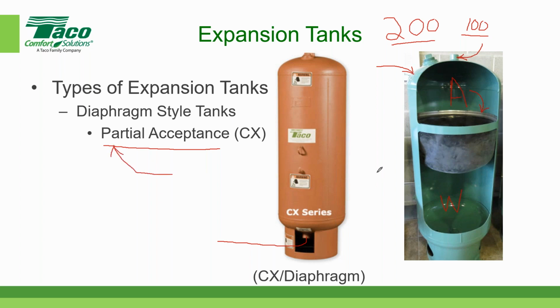Now, one of the major benefits to a diaphragm style tank is that they're very inexpensive. But the downside is that the bladder or diaphragm cannot be replaced. It cannot be serviced. If it should fail for any reason, you have to dispose of the tank. We cannot rebuild the tank and put a new diaphragm inside. So the downside is that it cannot be serviced, but the upside is that it's relatively inexpensive. And when you're talking about relatively small systems, the diaphragm style tanks are very, very economical. And because most people put in smaller systems, they can easily be replaced. You can take them out, put a new one in.